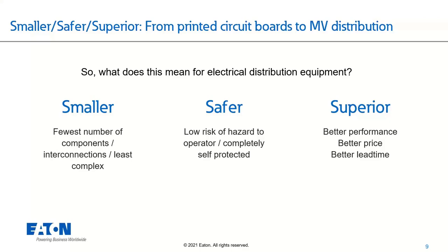I've often encountered customers where we are installing some means of protection and we're targeting, say, an 8 calorie per square centimeter incident energy, something where the user can now be in gloves and face shield. And in most cases, even if it is a level one PPE category, they're probably still going to wear the gloves and face shield. Why wouldn't you add that extra layer of safety? So those same customers will ask, what is the value proposition to get from a level two, where I'm wearing my gloves and face shield, down to a level one? Why would I need to do that if my users are already fairly safe?